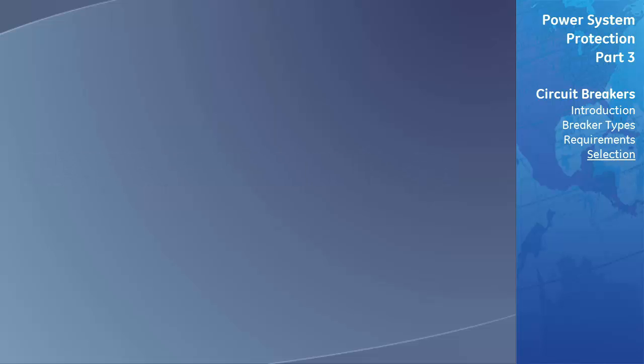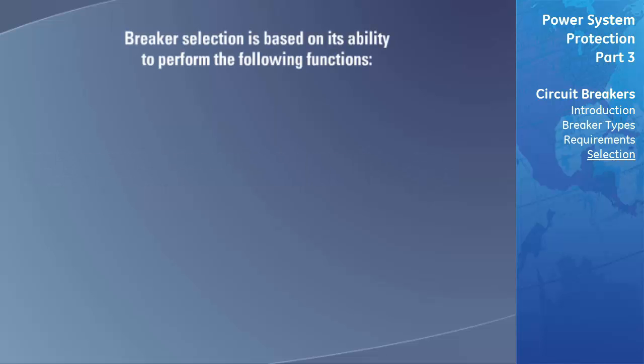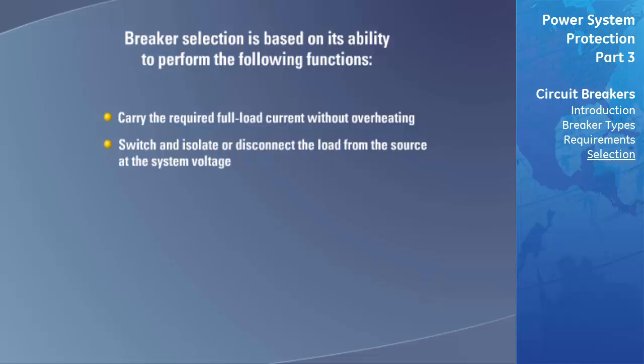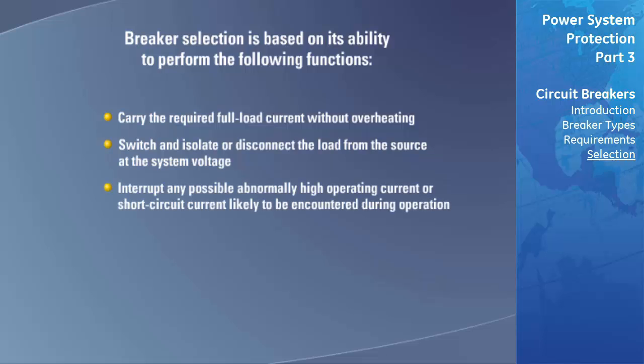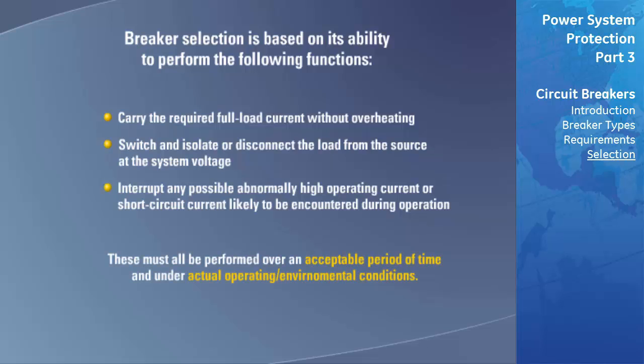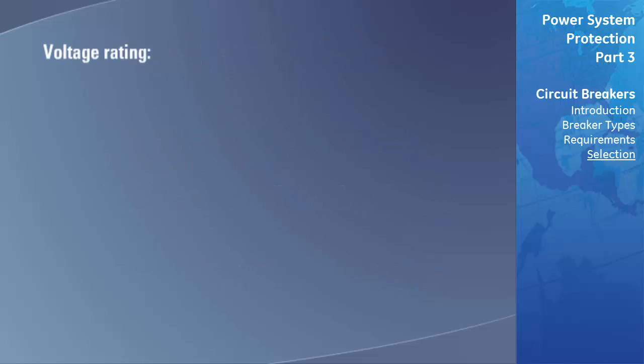The selection of any circuit breaker is based on its ability to carry the required full-load current without overheating, switch and isolate the load from the source at system voltage, and interrupt any possible abnormally high or short-circuit current likely to be encountered during operation. These functions must be performed over an acceptable period of time and under actual operating and environmental conditions. To select the correct breaker, we must examine its ratings.